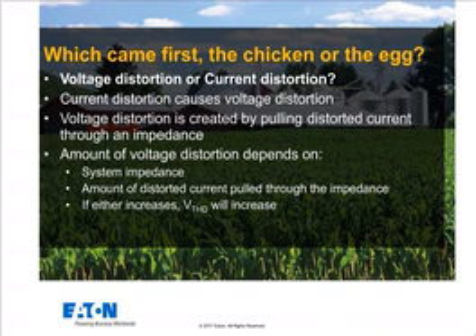Well, what we just talked about was the current distortion actually flowing back from the load up to the source, and it's an easy way to think about it that way. That's what causes the voltage distortion. So as we get more and more voltage distortion, we have more and more potential for misoperation, and that's why the utility companies care. It's not that they don't care if you screw up your own system with a lot of current distortion and the issues related to that. What they really don't want you to do is screw up the primary voltage on the incoming source, because then your neighbors or their other customers will complain about it, and then they have to deal with it. So the amount of voltage distortion depends on the system impedance and the amount of distorted current pulled through that impedance. If either one increases, then the voltage distortion will increase.